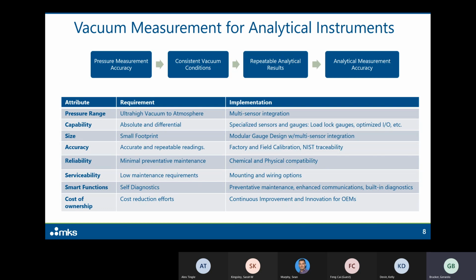Factory calibration is a must. Field calibration should be available. And of course, many laboratories looking for good laboratory practice certification will need traceability as well. Reliability is important. We want minimum preventative maintenance on the gauges, which means we have to look at the kind of analysis being done and make sure that we are chemically and physically compatible with the measurements being performed in the analytical instrument.